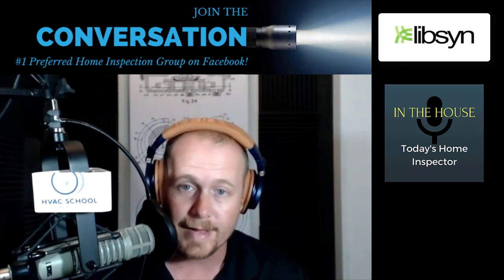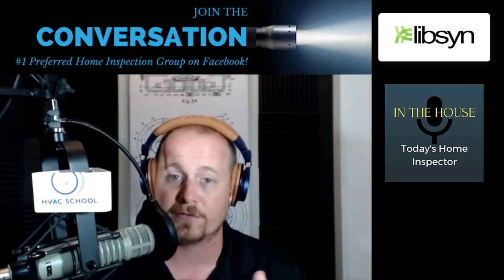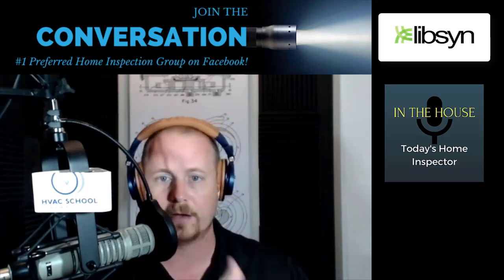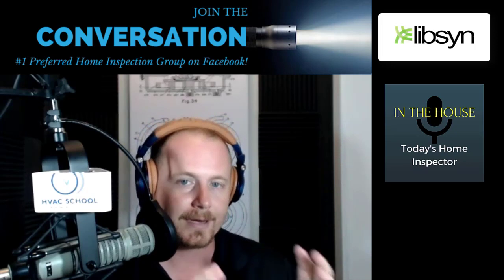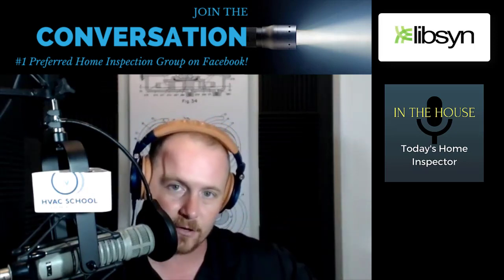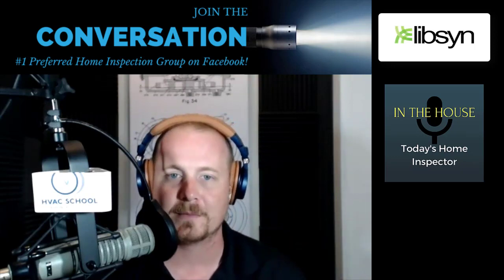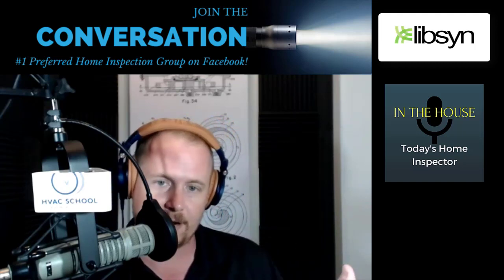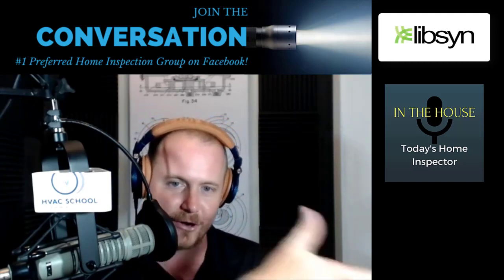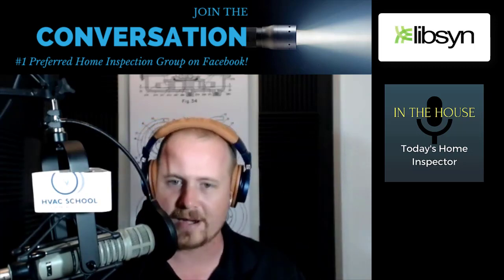Anything made of metal that has any reflectivity creates a big challenge, and this is true with flexible duct too. When you're looking at a flexible duct, either with an infrared gun or with a thermal imaging camera, you have to take really good care, because anything reflective, you're not seeing the temperature of that surface. You're seeing the temperature of whatever it's reflecting off of. So I don't want to see somebody hit the outside of a reflective duct with a thermal camera and say, wow, look at the temperature I'm seeing. Well, you're not seeing the temperature of that duct. You're seeing the temperature of whatever's reflecting off of that duct. That's how radiant heat works.